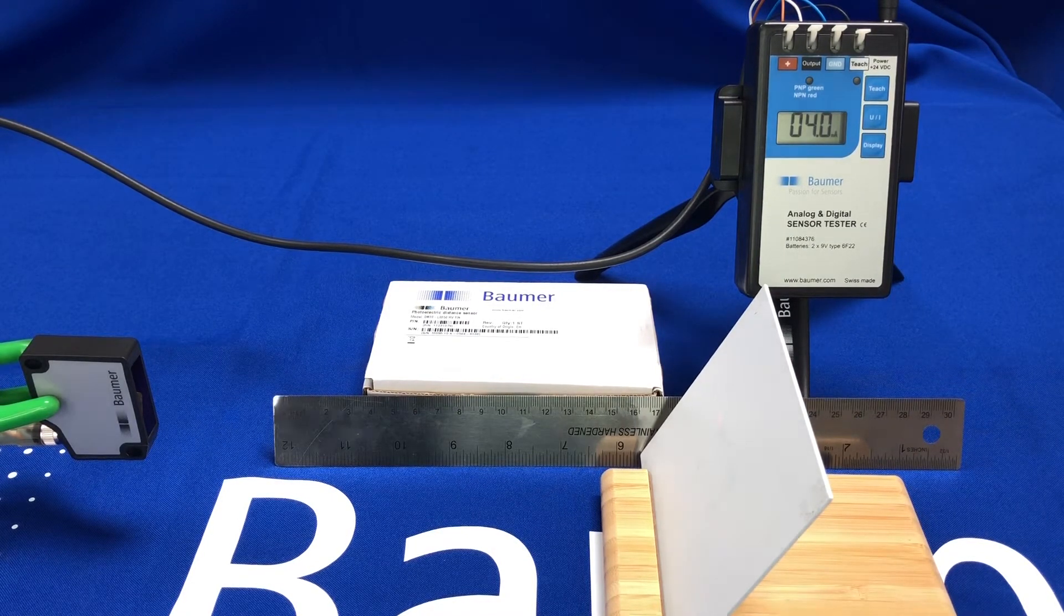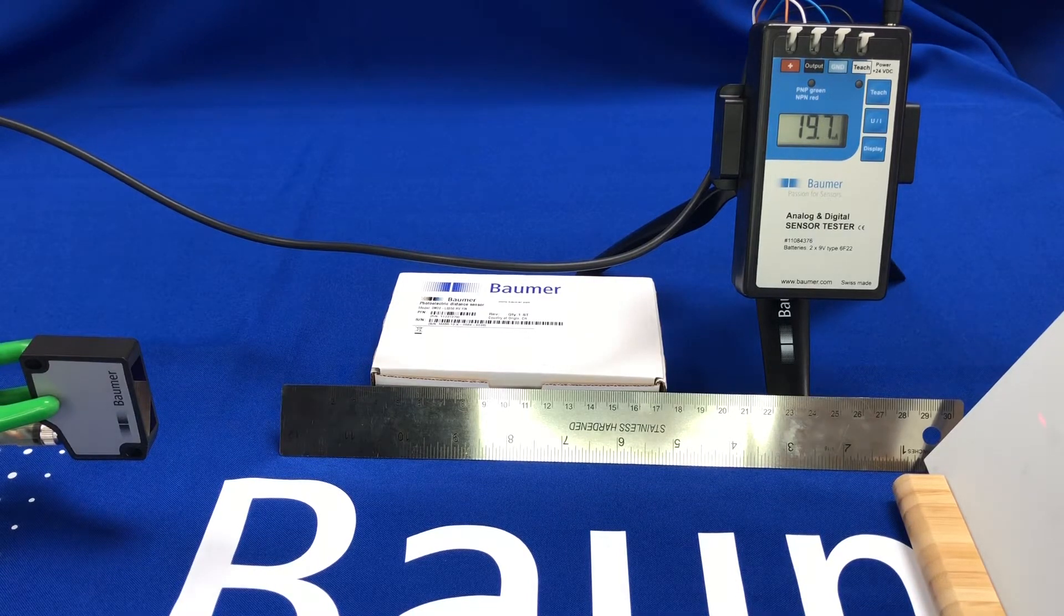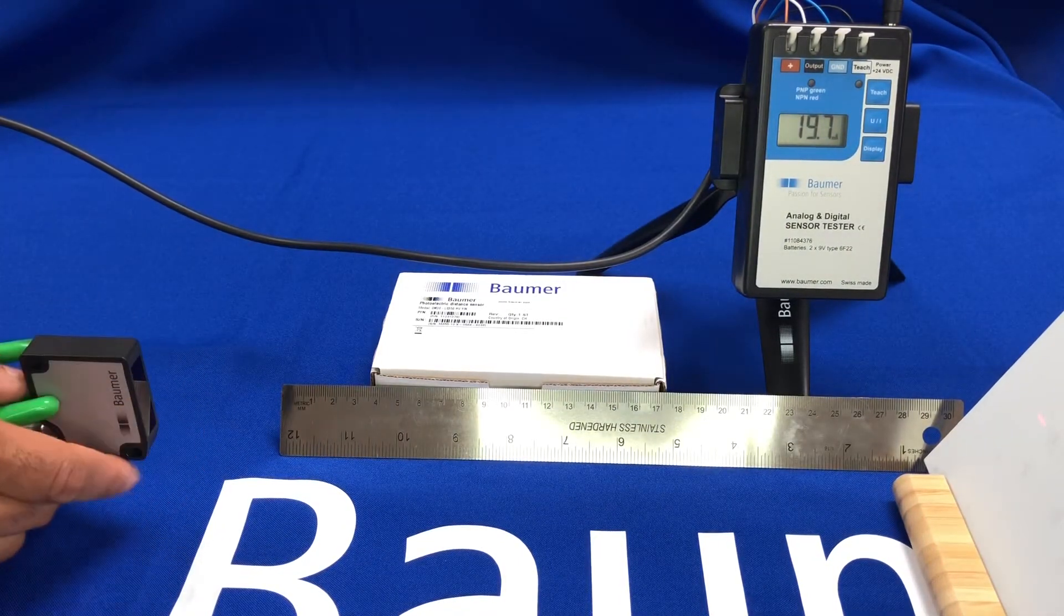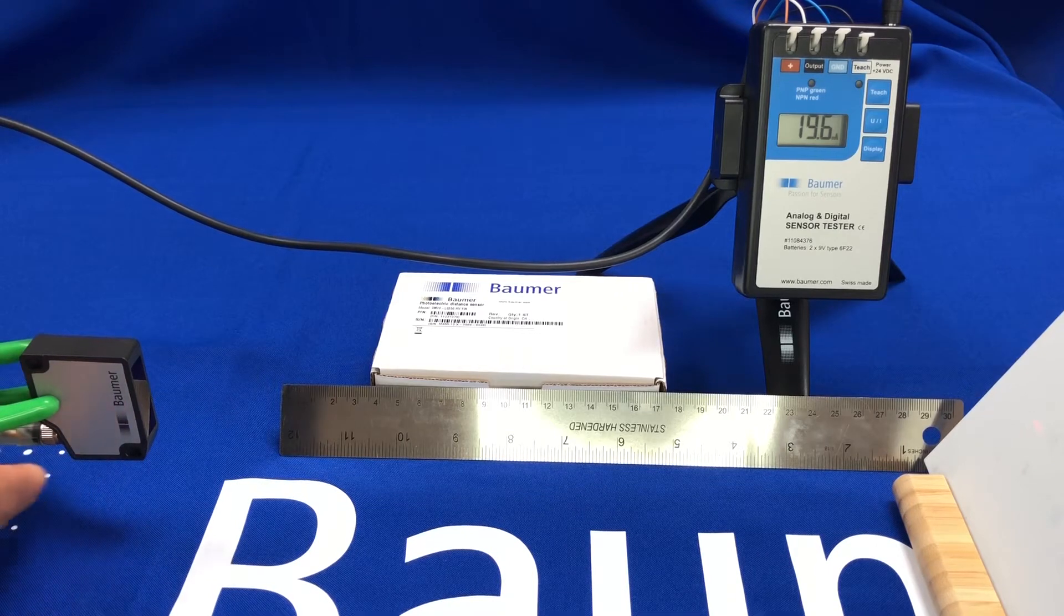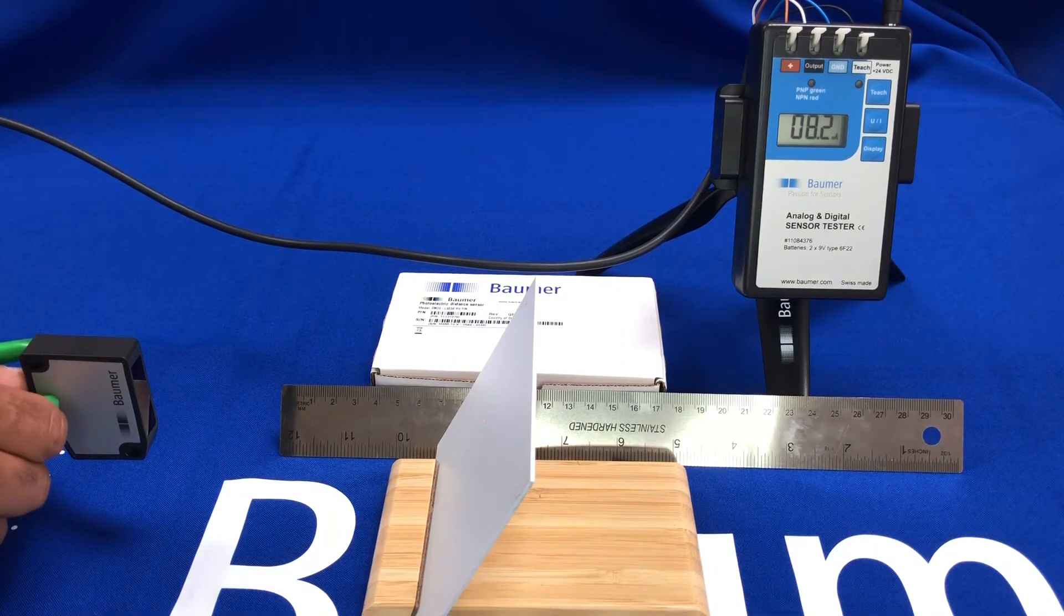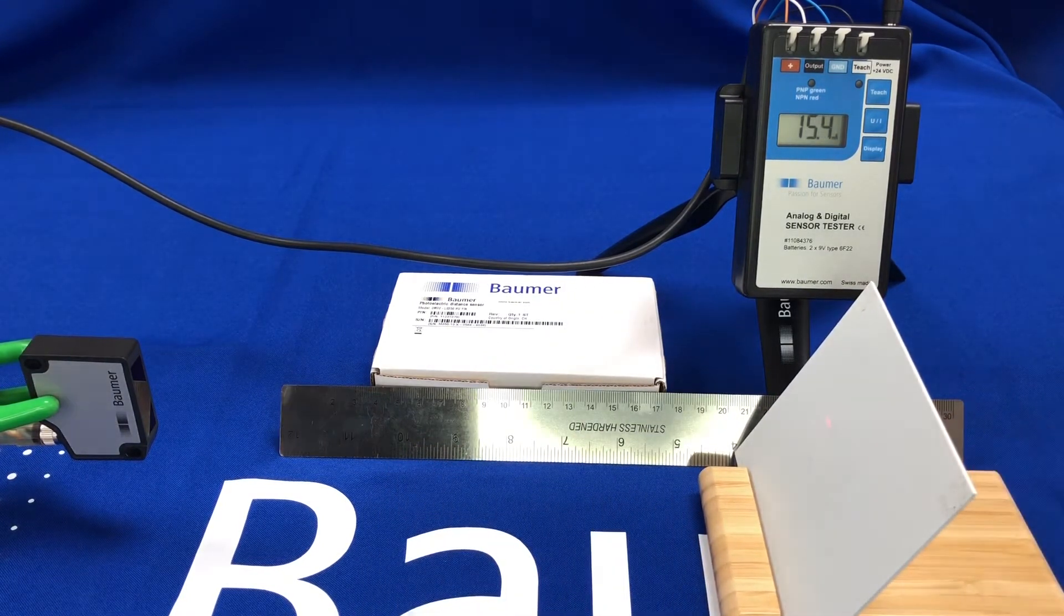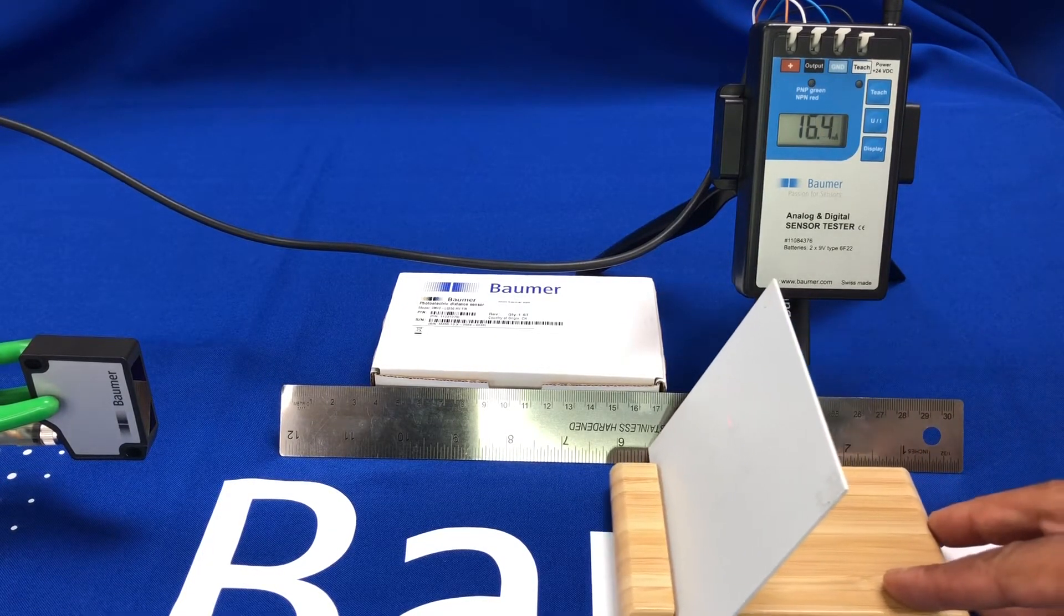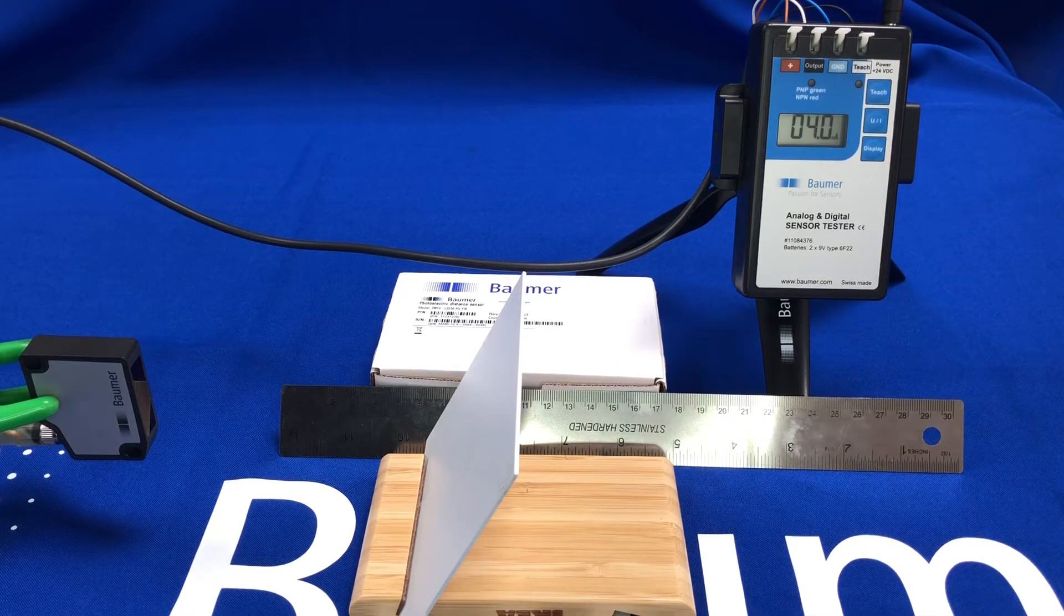To set a reduced range of the analog output, again very straightforward. You can do it via IO-Link of course, but by a simple teach button. You can see at full range we've got our 20 milliamps roughly. If I press the button at the back of the sensor and then press and hold for one, two, three, four seconds, I now can set one point here, press the button at the back, and then set it at my second range and tap again. There you can see now we've got our 20 milliamps all the way down to our 4 milliamps that I set there. Nice and easy to do.